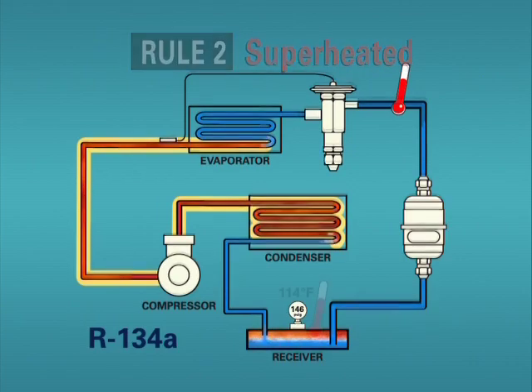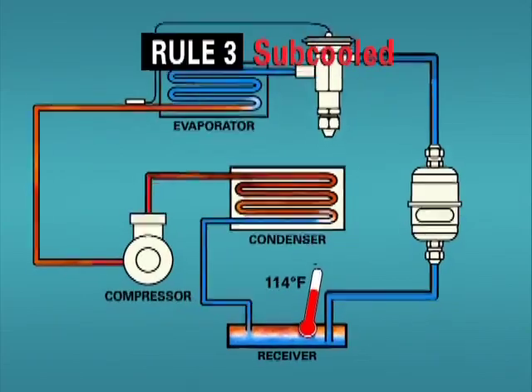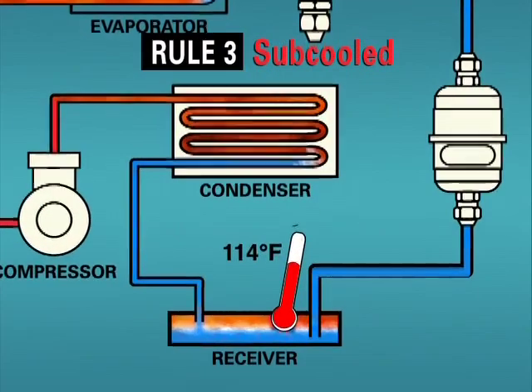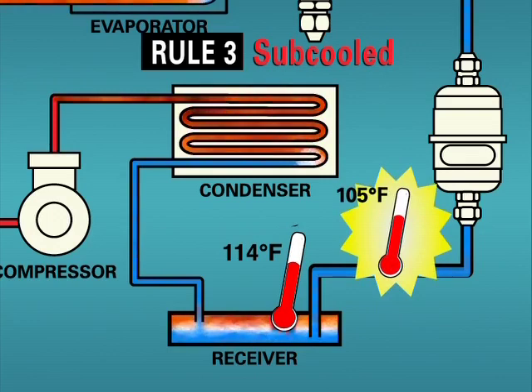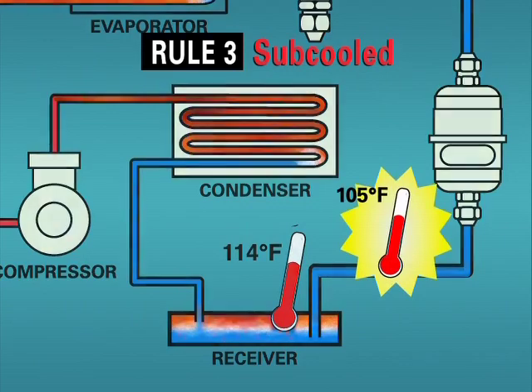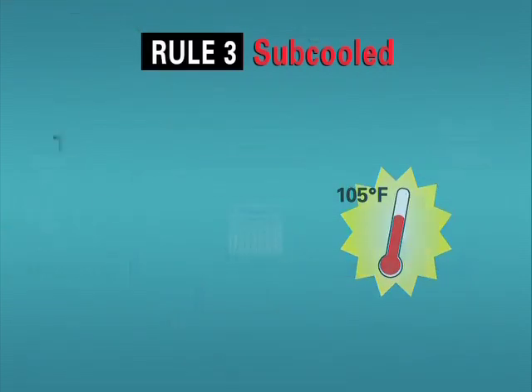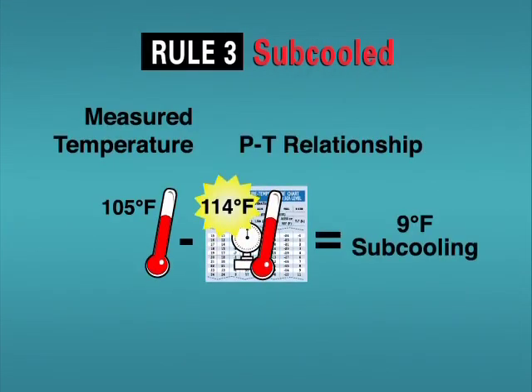Rule 3: We have subcooled liquid when our measured temperature is less than the saturation temperature indicated by our PT card. The amount of subcooling will be the difference in these two temperatures. Subcooled liquid will only be present in the liquid line which connects the condenser and evaporator coils of a normally operating system.